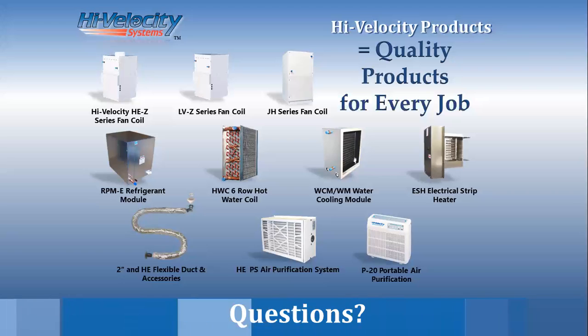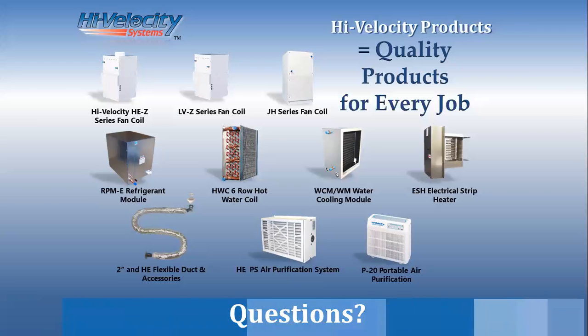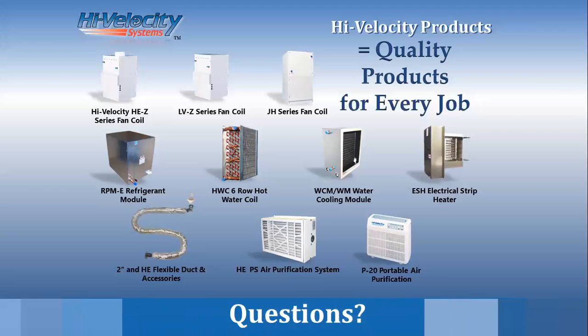Okay, another question popped up. I'm not sure if this was covered earlier, but what is the typical design friction rate on systems like this? We would typically design these at 1 inch of static pressure is how we like to design our high velocity products. 1 inch of static pressure is lower than other traditional high velocity manufacturers, but that's what we've found to be optimal for energy efficiency and noise control with our product line.